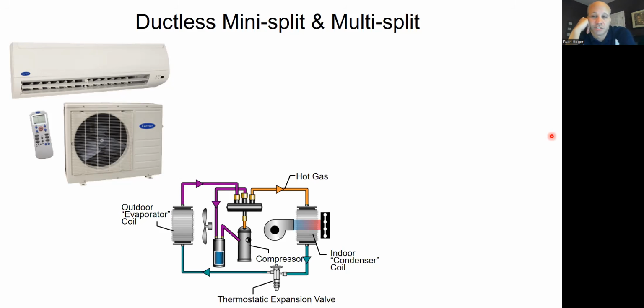The other applications are going to be where you do have occupant areas. So the common applications for these mostly are add-on places that didn't have cooling before. So maybe you got steam radiators in some kind of loft building, and now you're going to retrofit them and you're going to add some cooling. Instead of just adding cooling, why not add cooling with a heat pump? And you can run the heat pump and take some load off of the steam boiler and only run the steam boiler when it's below X degrees outside, and above X, you run the heat pump, right?